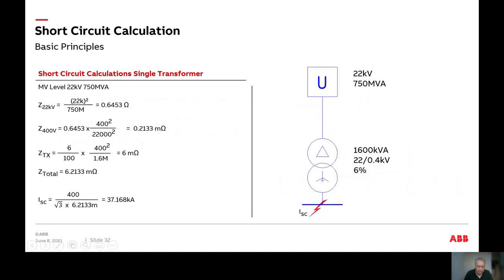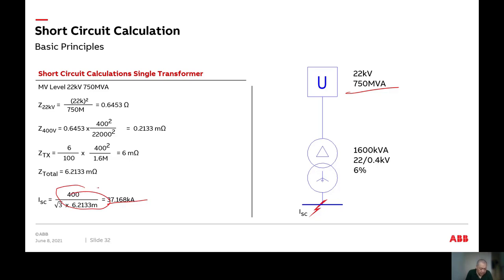For a simple calculation example: with my utility and a 1.6 MVA transformer, 22 kV to 400 V, 6% short circuit voltage, using the formulas given, I can find the total impedance and calculate the short circuit current. Using Ohm's law, the result is 37.2 kA — this doesn't change.